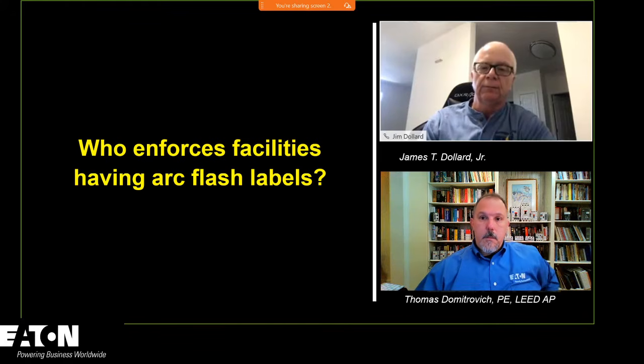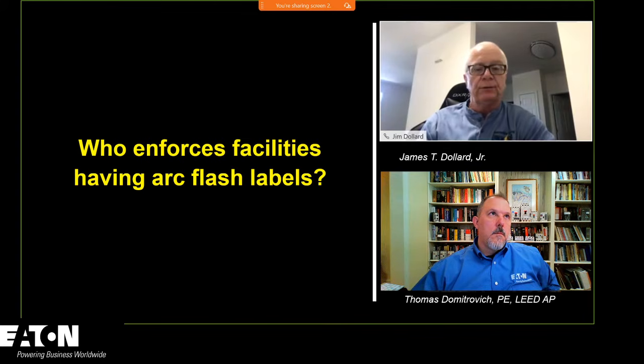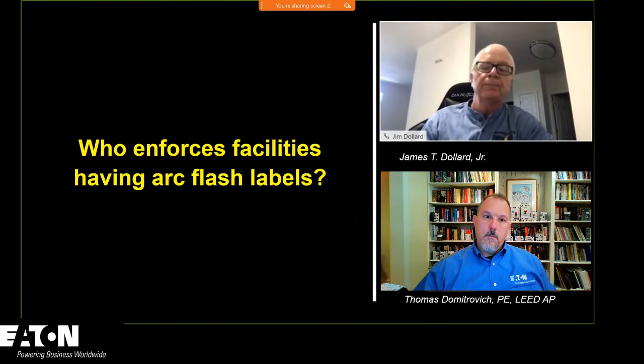NFPA 70E is a standard, and standards, by their nature and description in the NFPA process, are built to be incorporated into a code or a regulation, such as an OSHA regulation. But standing alone, they are not a code. One thing we look at is 70E and NFPA 70, the National Electrical Code, there's a very clear line of demarcation between them. Installation requirements go into NFPA 70, the National Electrical Code. Anything electrically safe work practices related goes into NFPA 70E. For that reason, a few cycles back, all the installation requirements that were in 70E, which at one point was like a cliff notes for the NEC, were removed.